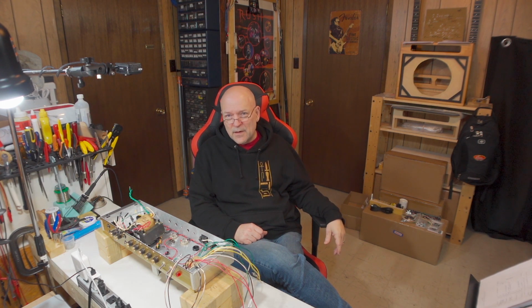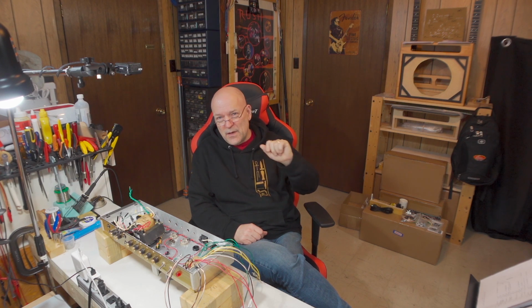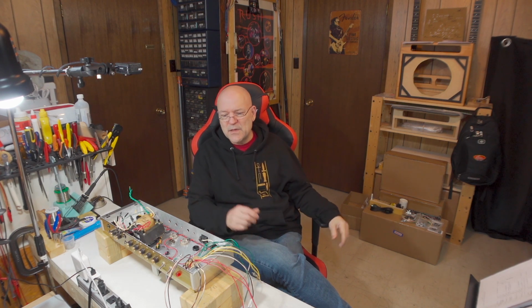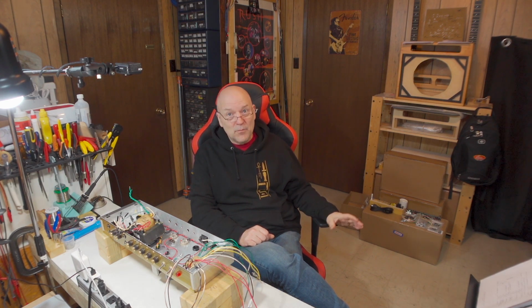rewire that in. I'm not going to show wiring it in, I'll do it off camera, because the procedure is no different than what I did before. As I said earlier in this video when troubleshooting, the indication of the damage was right there on the transformer. It doesn't necessarily mean that's where the problem is. My assessment was that the transformer was faulty, and all the symptoms and troubleshooting seemed to indicate that, but I was wrong. I made a mistake.